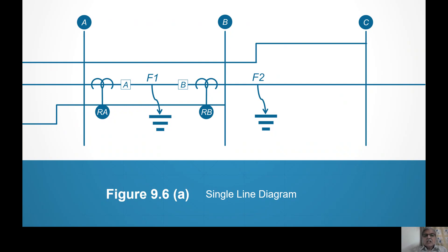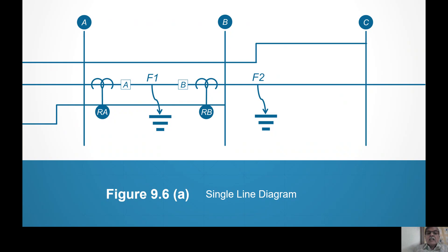That aim was not fulfilled in distance protection or overcurrent protection. Now that aim is fulfilled here. The first zone of relay RA extends up to 120% of line section AB, so it crosses B. Similarly, the first zone of relay RB will cross A — it will be 120% of BA. Second and third zones are as usual with distance backup. If there is a fault in the second or third zone, distance will give backup. That is the main advantage.